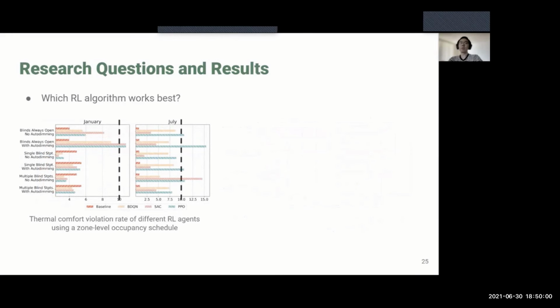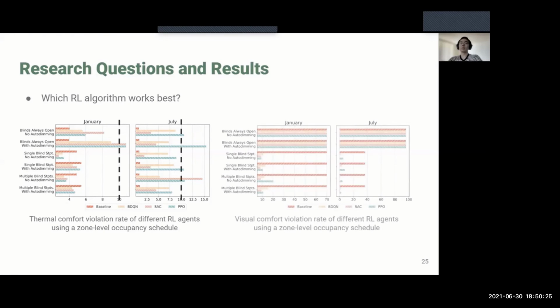Considering thermal comfort shown on the left figure, recall the threshold for thermal comfort violation rate is 10%. If we focus on July, PPO, the green bar, cannot satisfy the thermal comfort in the cooling season for most cases, with an average thermal comfort violation rate of 10.8%. In contrast, SAC, the pink bar, exceeds the threshold only once, and BDQN, the orange bar, can always maintain the thermal violation rate under the threshold.